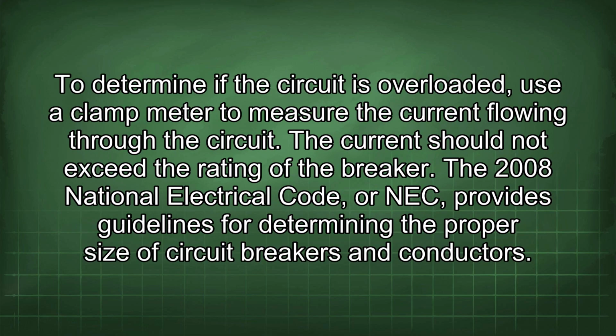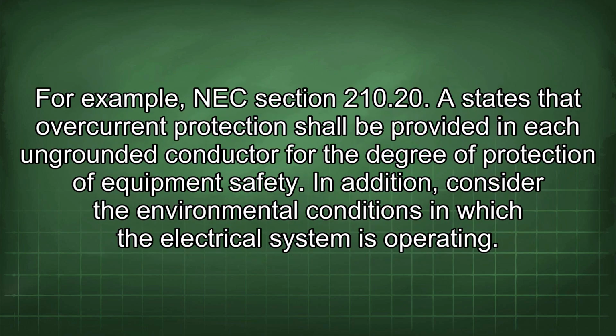To determine if the circuit is overloaded, use a clamp meter to measure the current flowing through the circuit. The current should not exceed the rating of the breaker. The 2008 National Electrical Code, or NEC, provides guidelines for determining the proper size of circuit breakers and conductors.